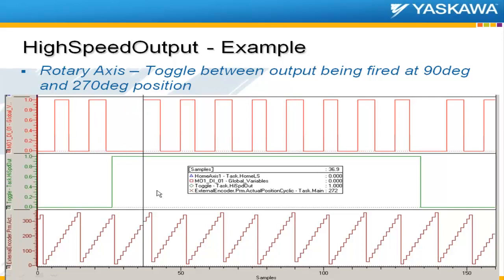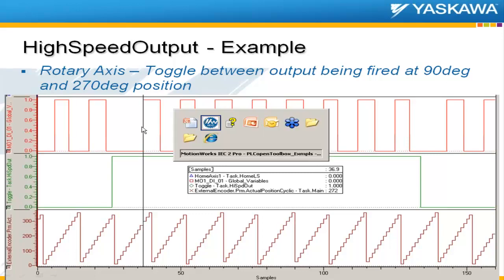If we look at the trace, here is the high-speed output toggling. With the toggle input on, my target is 270 degrees. Here is the external input going from 0 to 360, firing at about 270 degrees. The scope actually shows 272, which is a little misleading because the scope is tied to the task rate — so the data may not perfectly reflect what's truly happening. We would need an external scope to really verify the 13-microsecond response, but it does happen at that speed.